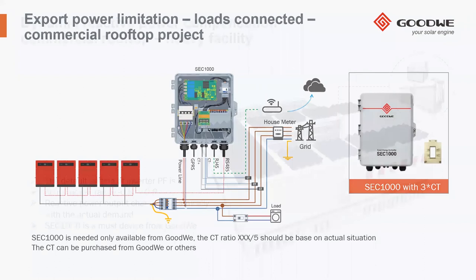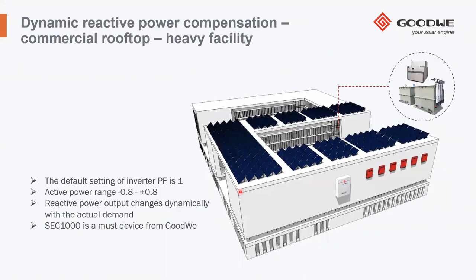Another feature, again, this is very common in Italy, in Germany, in Spain, is the capability of the system to handle the reactive power. This is mandatory in many situations, and our system is capable of doing that automatically. So it is able to adjust the reactive power. And this is extremely important anytime the grid operator requires this parameter to be adjusted. This is another functionality which is already integrated in our MT system.